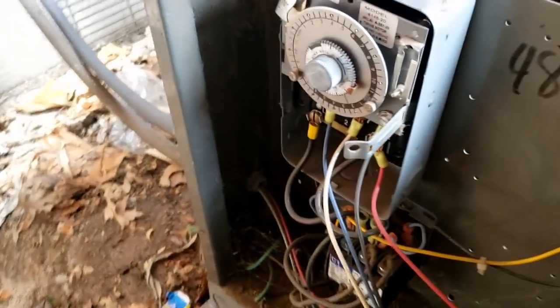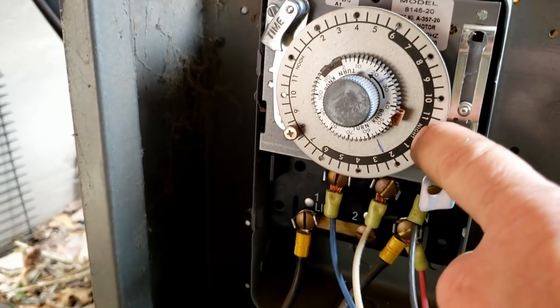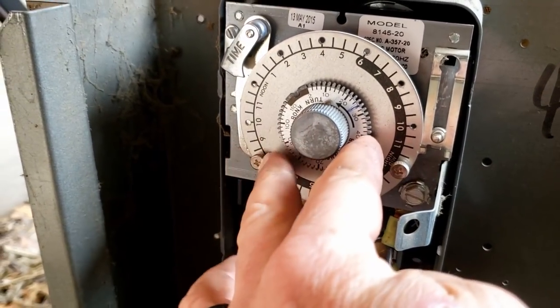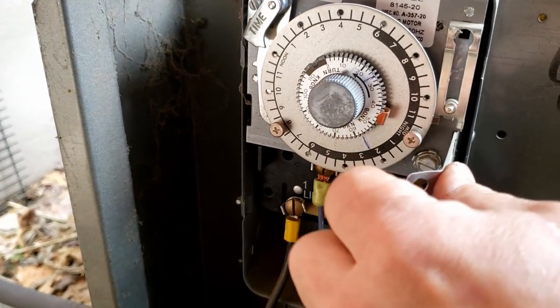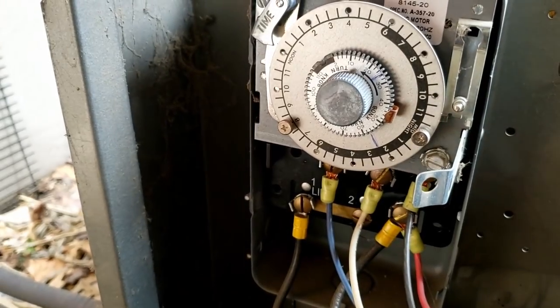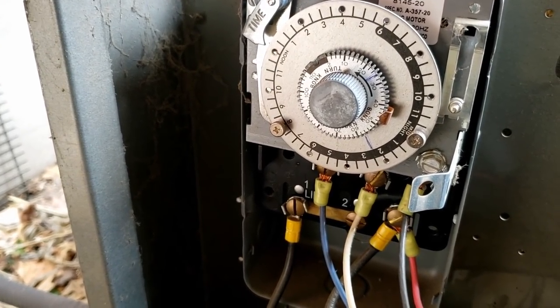I just now had a chance to look closer at this defrost clock, but it's a little bit whopper jawed there, and like he said, time was off. May not do you a whole lot of good, so we're gonna even those out. May actually take it to 3 instead of the 2.